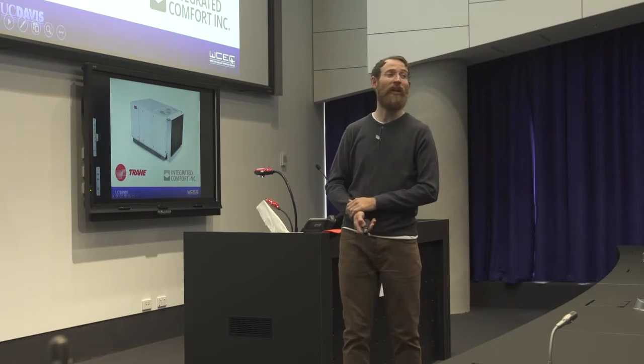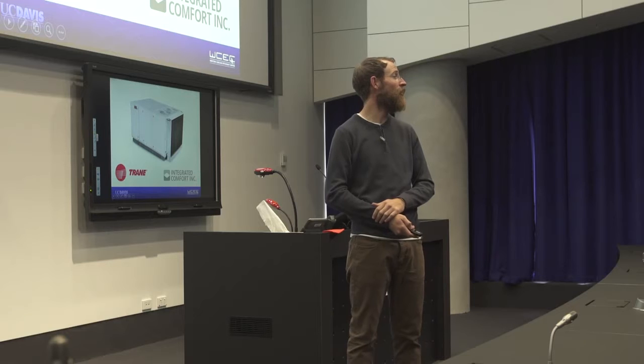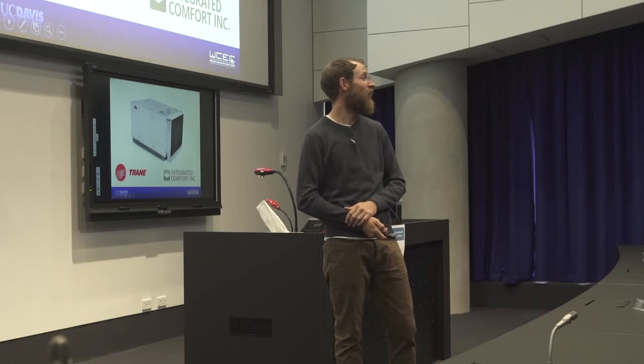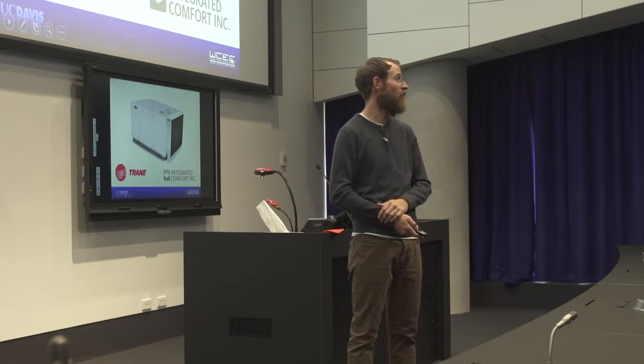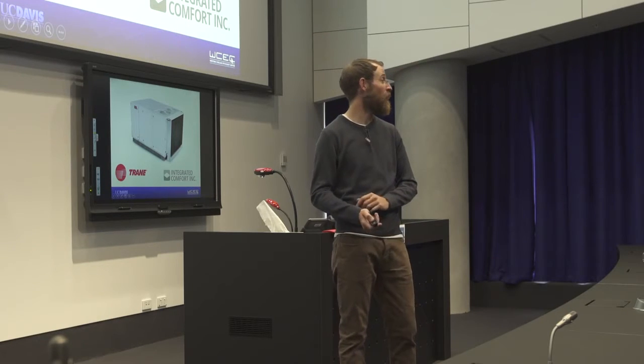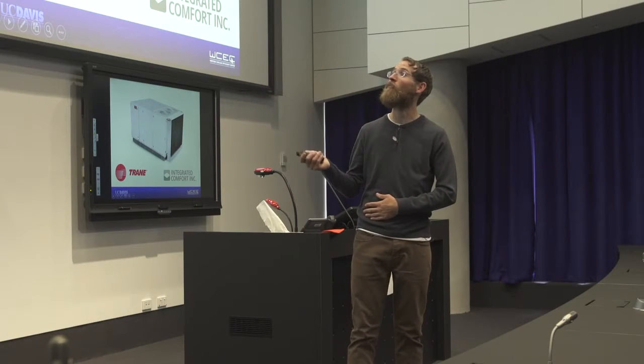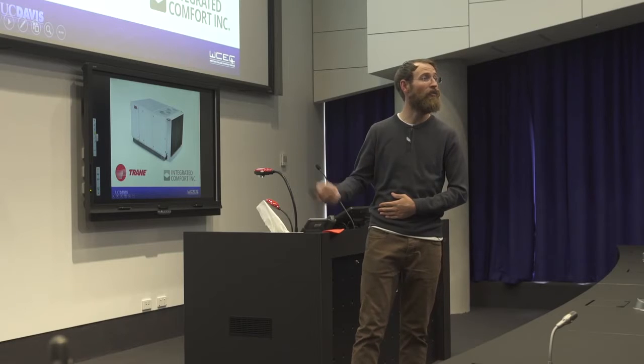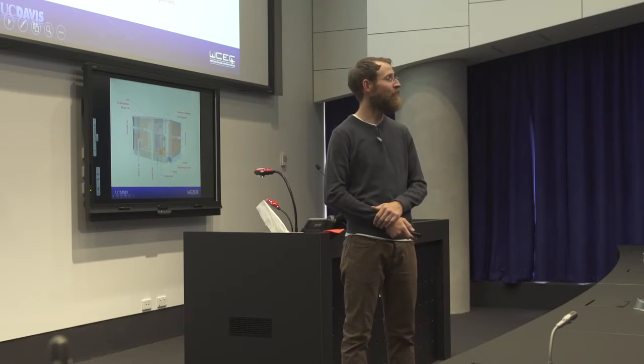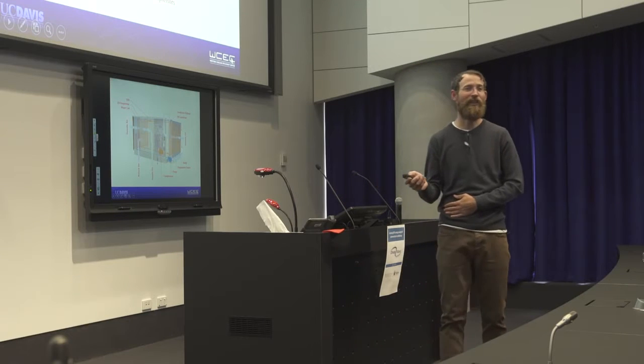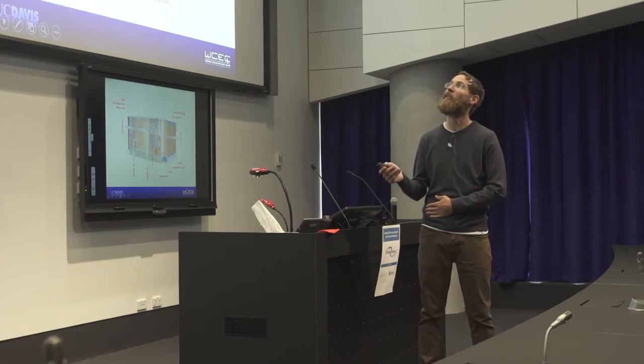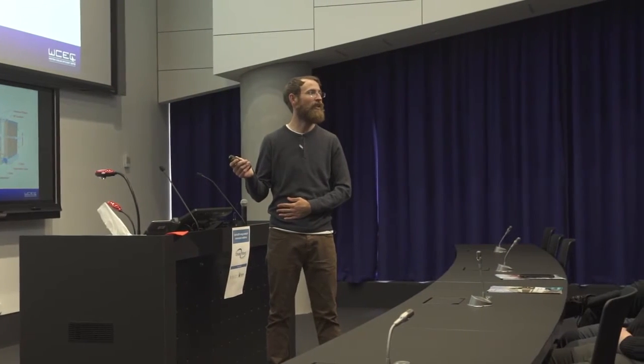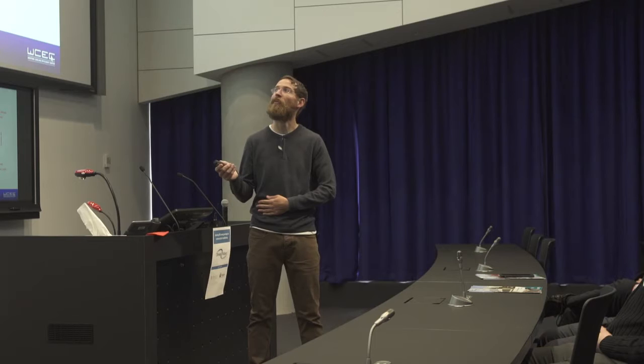There's one more technology that I'll point out, which has formed another core of our research. There's another type of hybrid rooftop packaged air conditioner that uses indirect evaporative cooling together with vapor compression, but in a different way. It was tested through the Western Cooling Challenge as a collaboration between Trane and a California company called Integrated Comfort. And here's how the system works. It's a different approach to indirect evaporative cooling. It's designed very specifically as a retrofit to an existing rooftop air conditioner, and it can't really operate as an indirect evaporative cooler on its own, the way that Climate Wizard or Colorado system might.